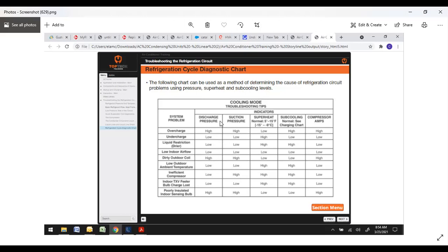A dirty outdoor coil is going to give you a high discharge pressure and a high suction pressure. A lot of times, a dirty coil will still cool on a mild day. It just won't cool for anything during a hot day. Because what you're seeing is not real pressures, because they're being tricked by the dirty outdoor coil. So your superheat will be super low because you're not really cooling like you should. Subcooling will be low, and a dirty outdoor coil is going to cause your amp draw to go up considerably because the unit can't breathe. Now, once you clean the outdoor coil, make sure you wait, let your system run, and recheck your charge. Because once that coil is clean, you may have to make some adjustments.